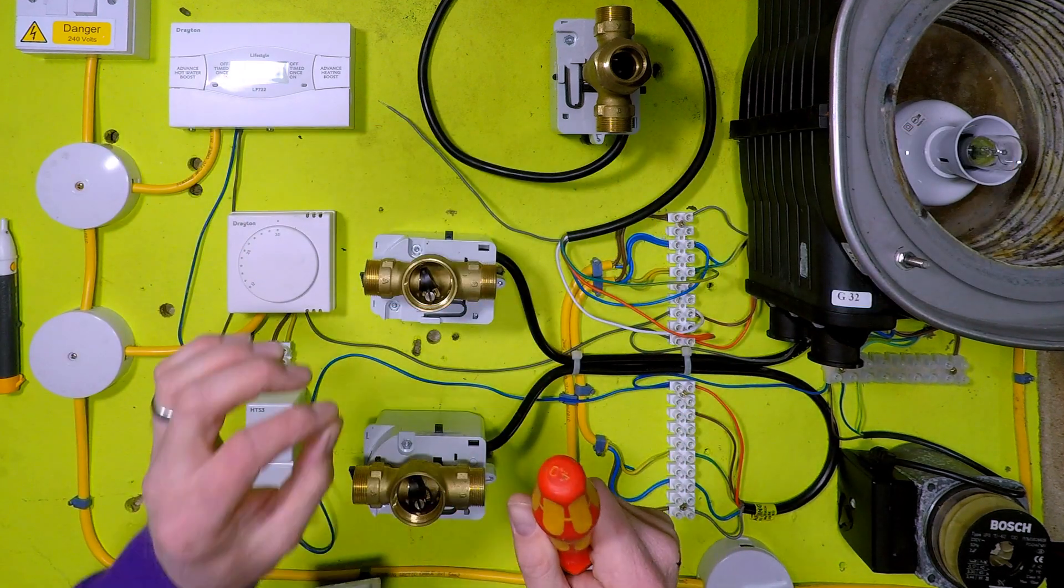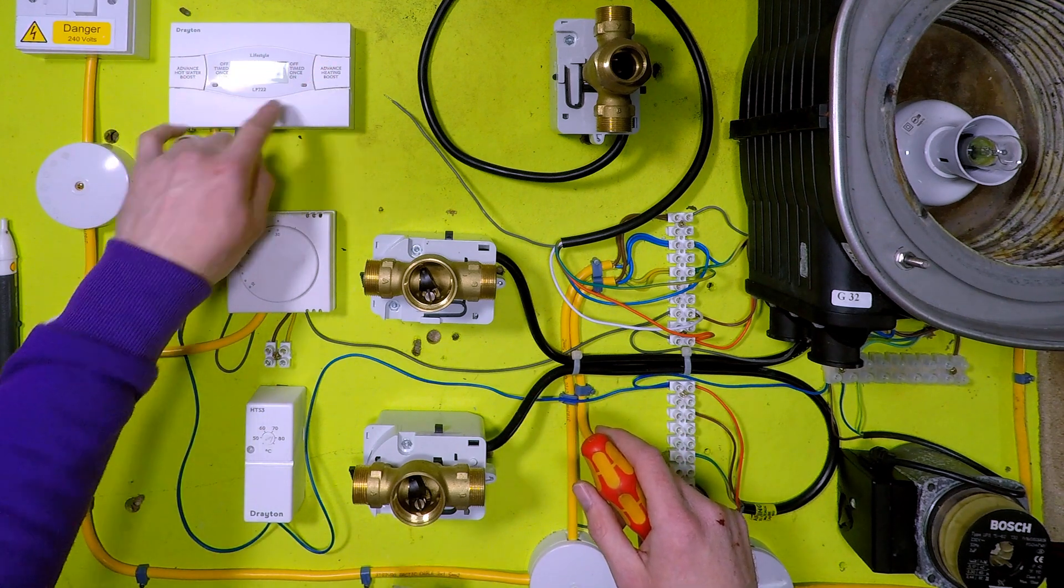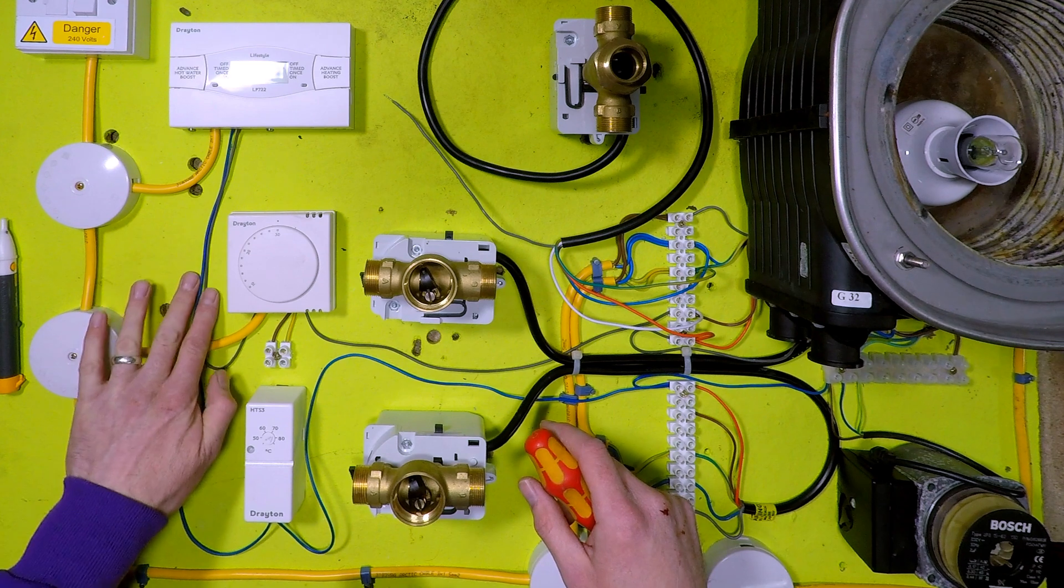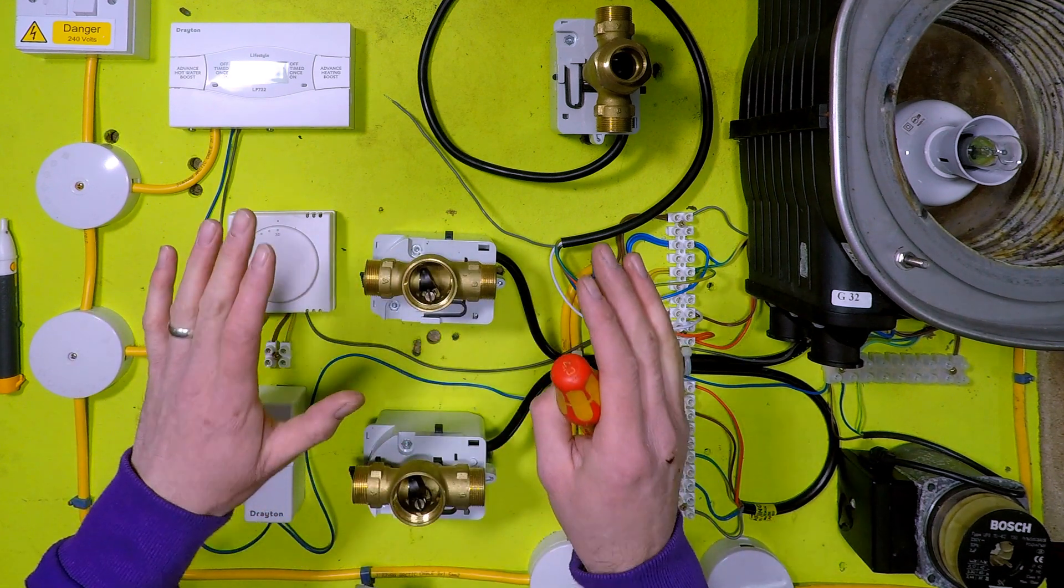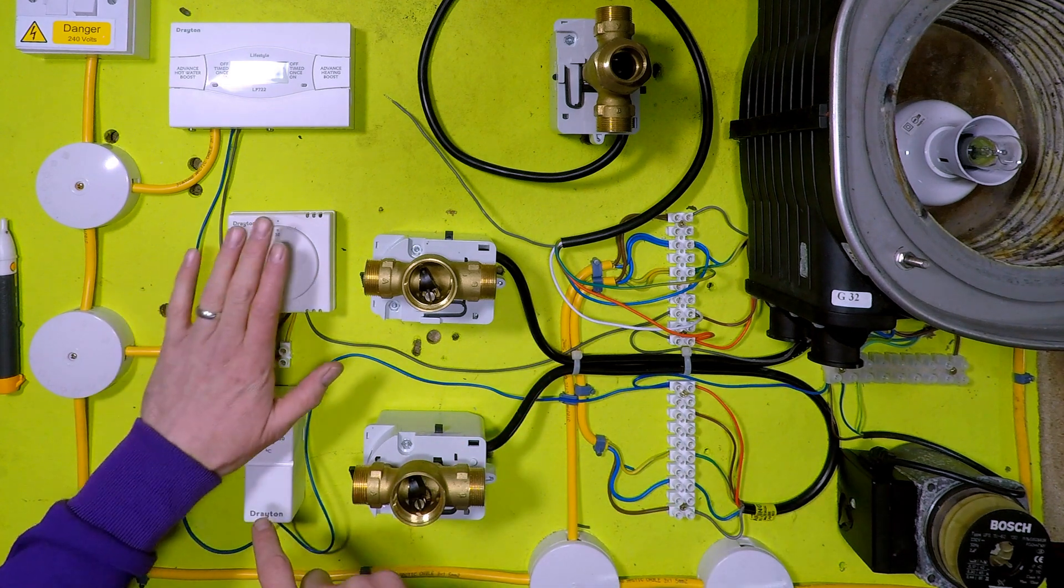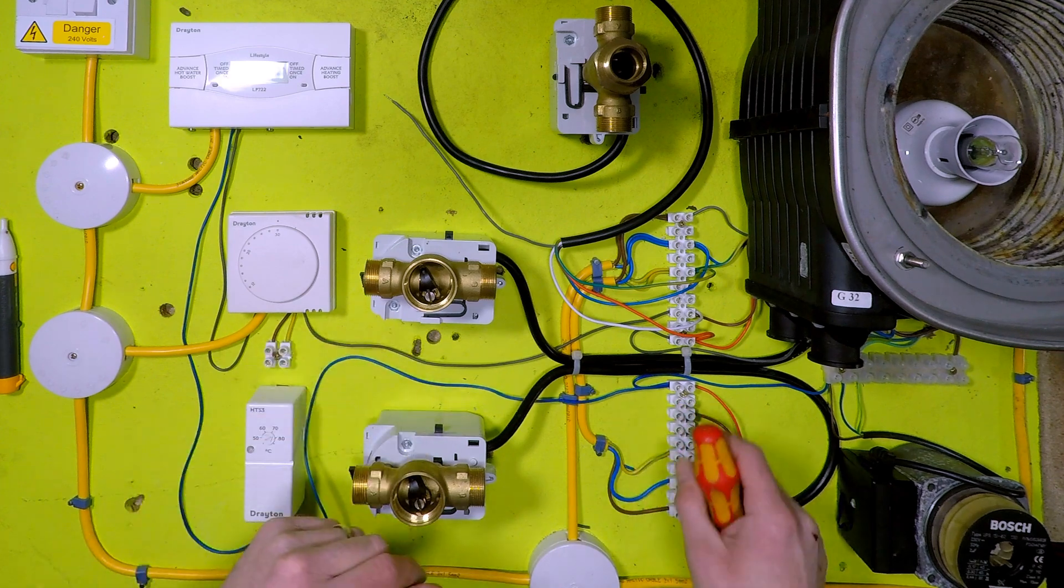So that was hot water only. Now we're going to go on to heating and water. What happens is the power comes - you have both of these wires have power, okay? Goes into both cylinder stats. Now this is when there's a demand. Heating and water are both demanding. Cylinder stat and room stat want heat. The power then comes from the cylinder stat and the room stat.